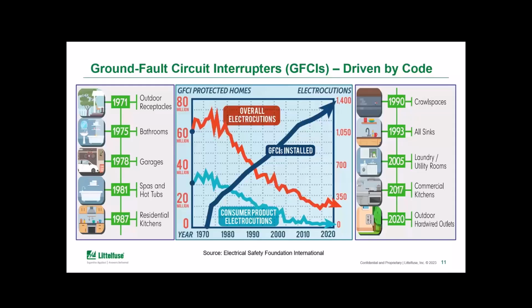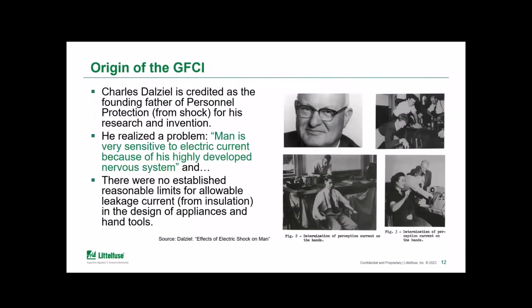At that time, there was increased usage of higher amperage equipment, and new GFCI devices were coming on the market that could offer protection up at that 100 amp level. One example of an application that was affected, shown there, was commercial kitchens. The intent was to protect people using the deep fryers, dishwashers, and ranges that were reaching load currents up to that 100 amp level. And so you can see there really will continue to be changes to GFCI requirements as technology changes, because more and more of our equipment is now becoming electrically driven.